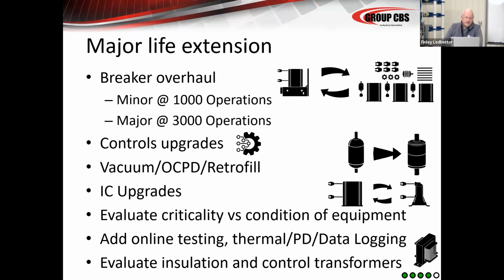At this point, you really have to evaluate the criticality and the condition of your equipment to determine what you do. You might want to add some online testing, thermal, PD or data logging capabilities if you don't have it. And you want to completely evaluate your insulating system and the control transformers in your system. And that's coming up. That's in the next 25 years. If your equipment's 40 or 50 years old, these are the things you should be looking for and planning for right now.